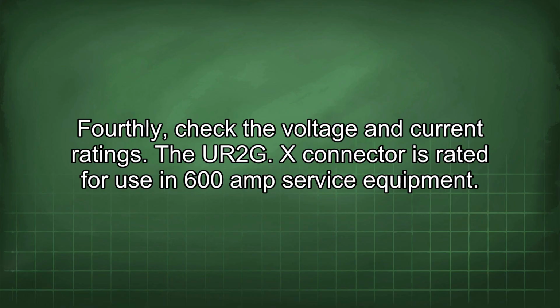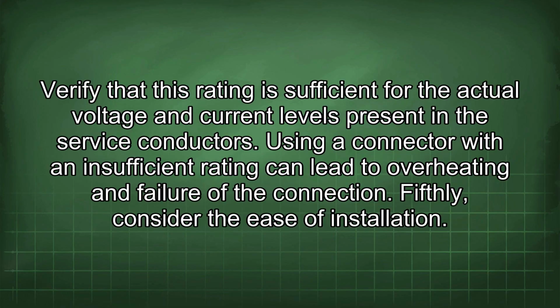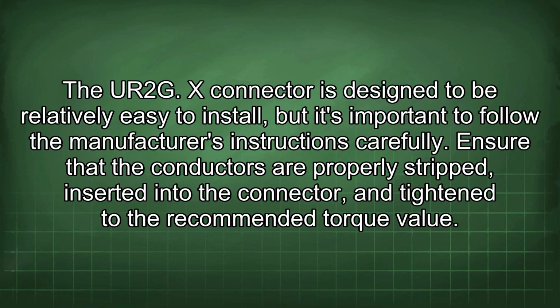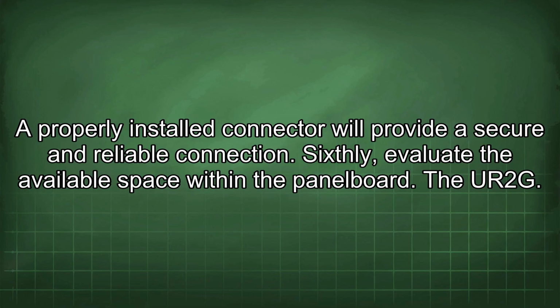The UR2G X connector is rated for use in 600 amp service equipment. Verify that this rating is sufficient for the actual voltage and current levels present in the service conductors. Using a connector with an insufficient rating can lead to overheating and failure of the connection. Fifthly, consider the ease of installation. The UR2G X connector is designed to be relatively easy to install, but it's important to follow the manufacturer's instructions carefully. Ensure that the conductors are properly stripped, inserted into the connector, and tightened to the recommended torque value. A properly installed connector will provide a secure and reliable connection.